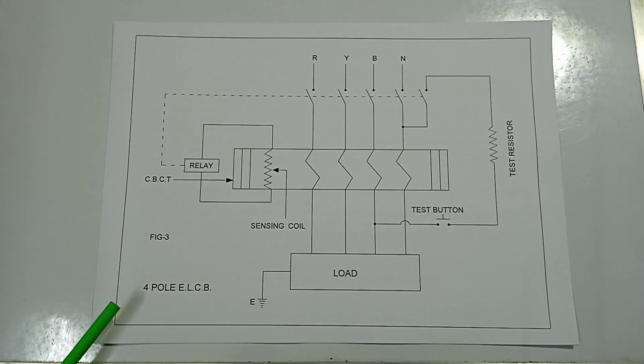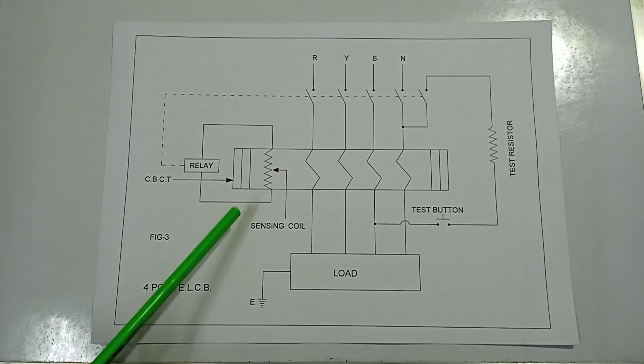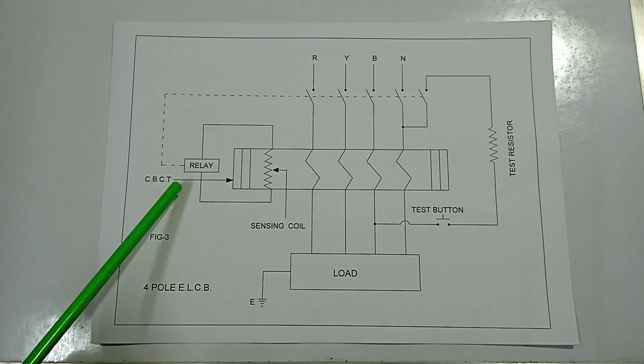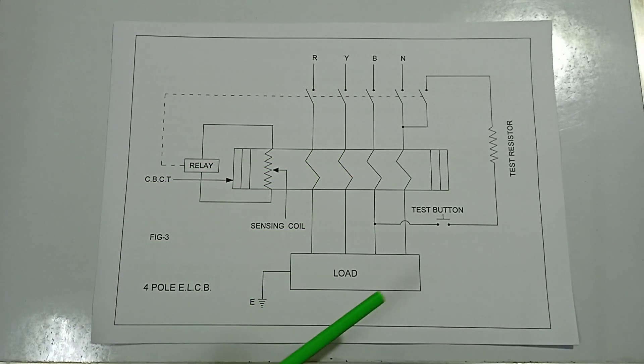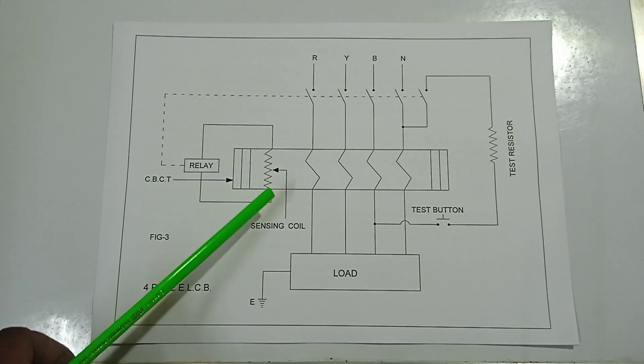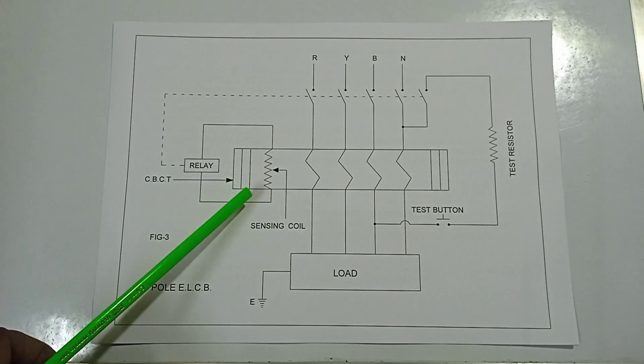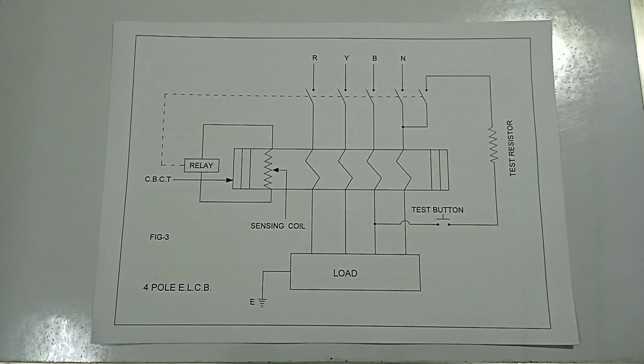Figure 3 shows a four-pole ELCB with its CBCT. The secondary of the CBCT includes the sensing coil and relay. The R, Y, B phases and neutral all pass through the CBCT core toward the load. There is also a test button. When any earth leakage current is detected, the sensing coil energizes the relay, which activates the circuit breaker.